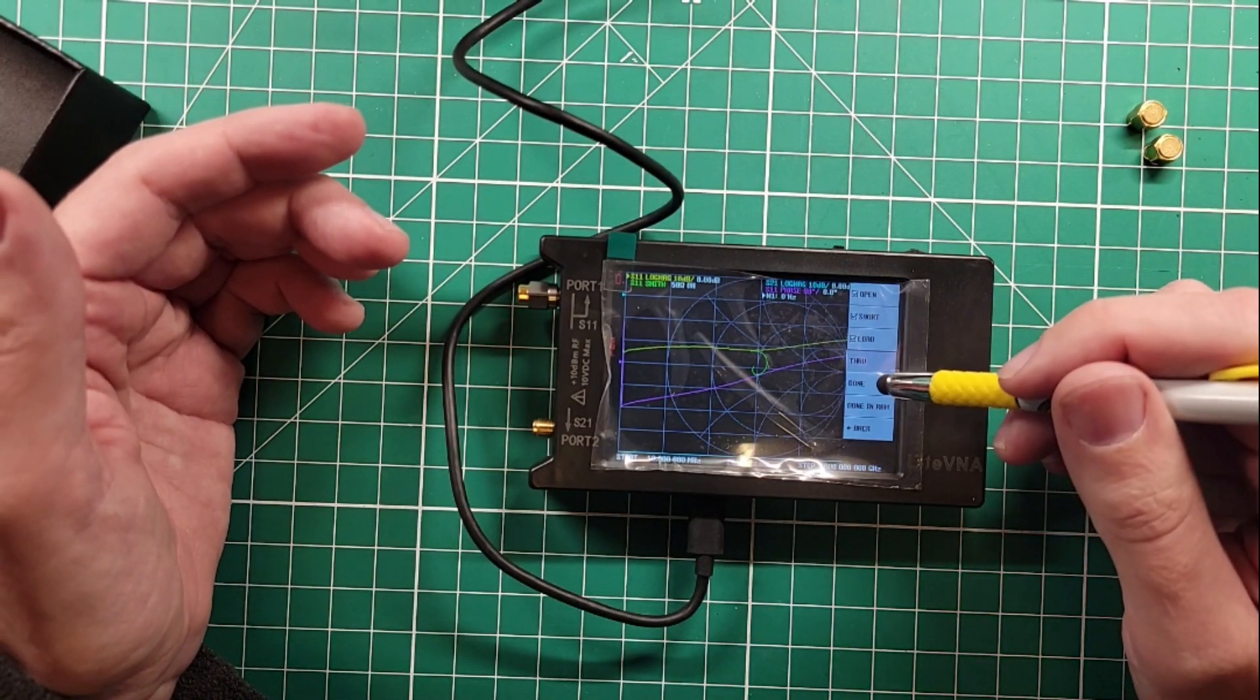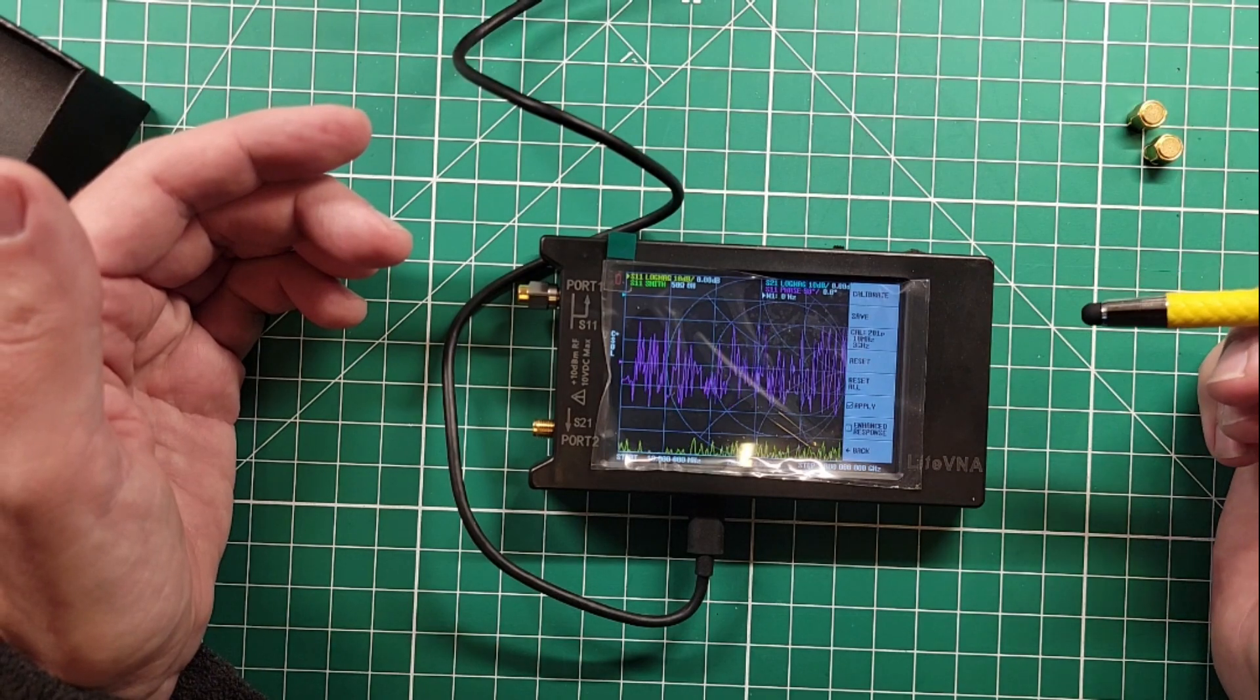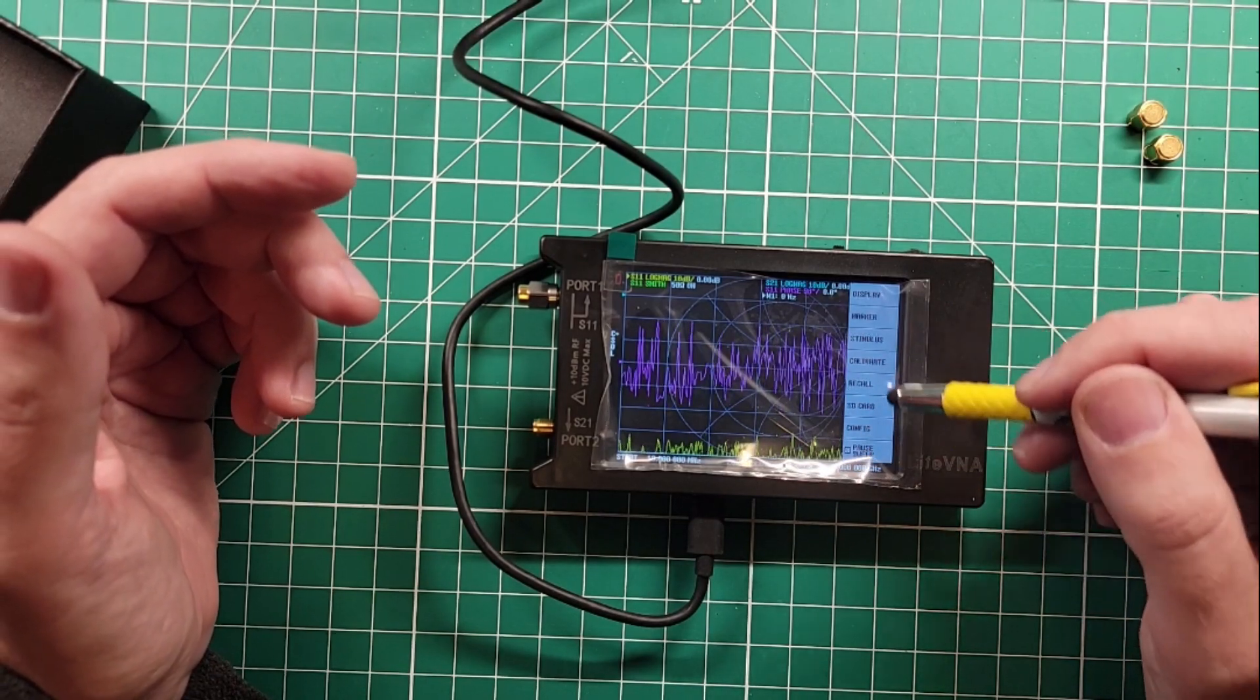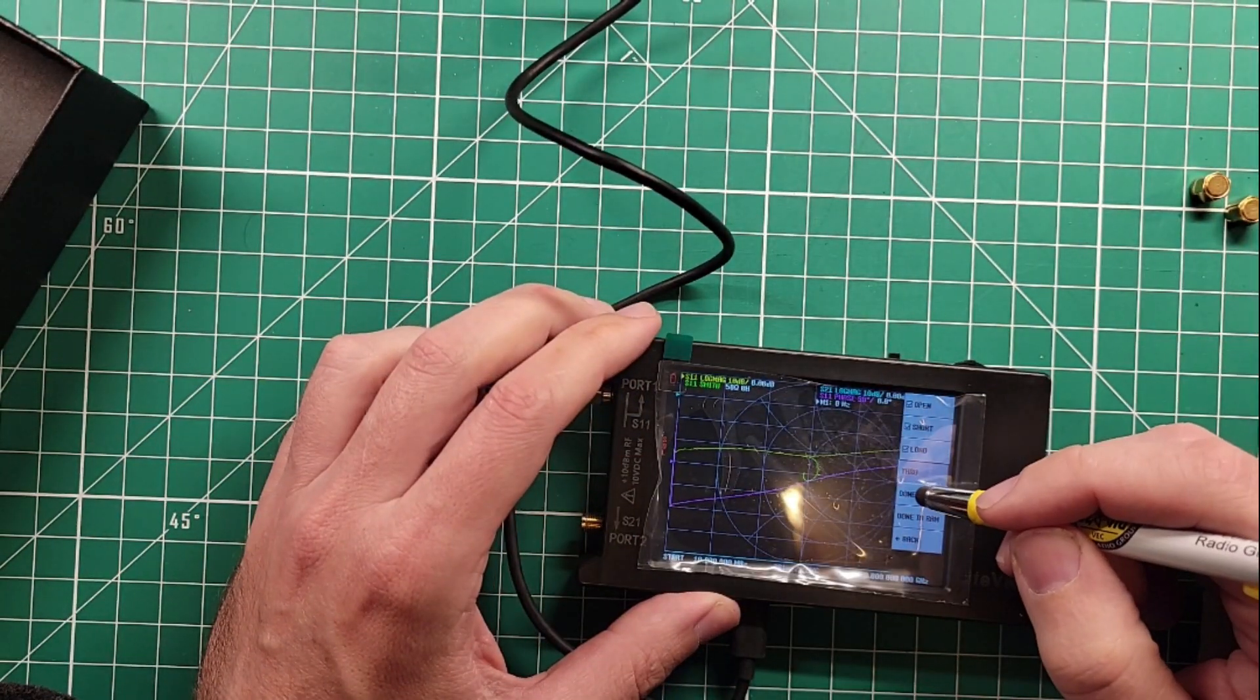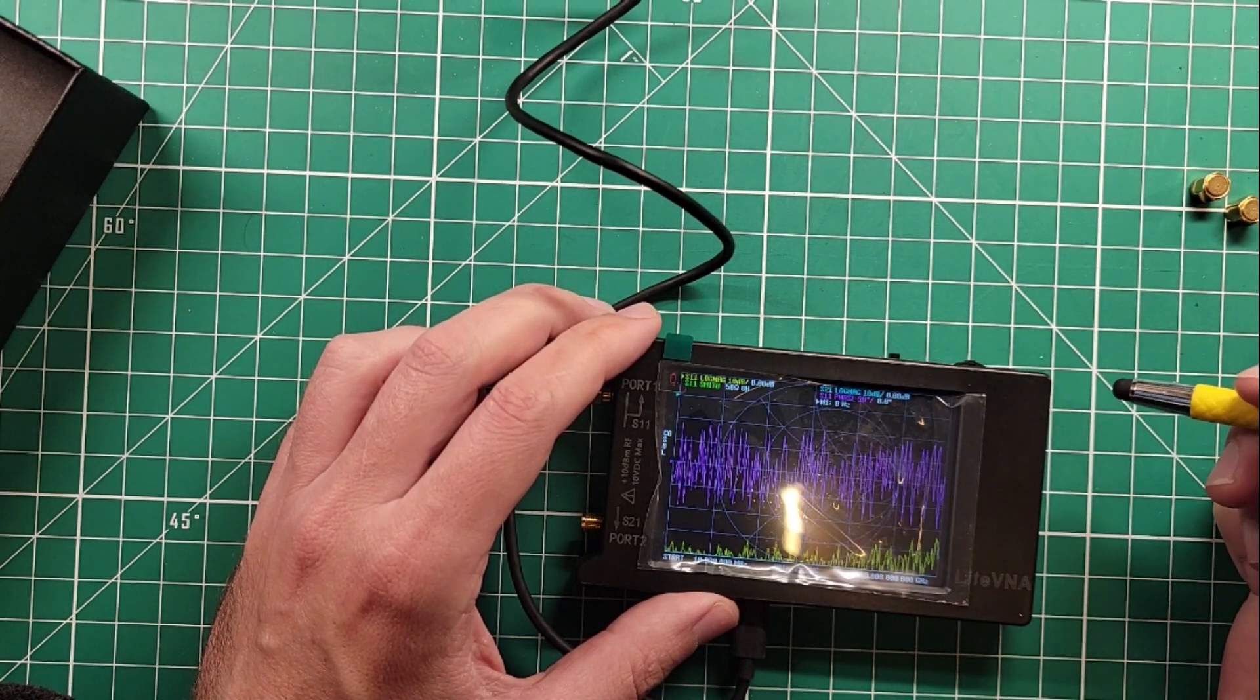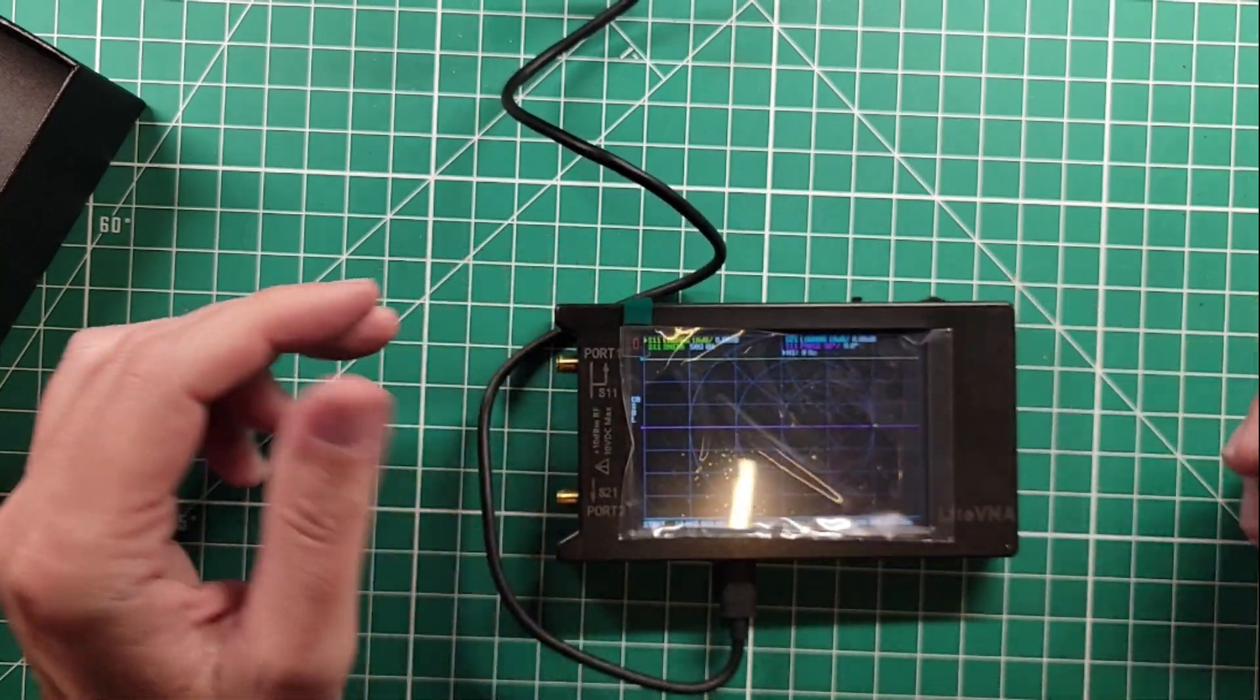And again, no indicator that I actually did the thing until it's done. I'm not going to do a through test. That's fun. And then there's done. And there's done in RAM. Done in RAM is new. Let's try done in RAM. So it's automatically applied. And it doesn't really give you the ability to save it as you're going through the process. Let's go back. Let's do calibrate again. I'll speed it up this time. And we'll just do done this time. So done gives us the options to save. I'm going to save that as option zero. It's now been calibrated. So you can recall option zero and the device has been calibrated as you recall those things.